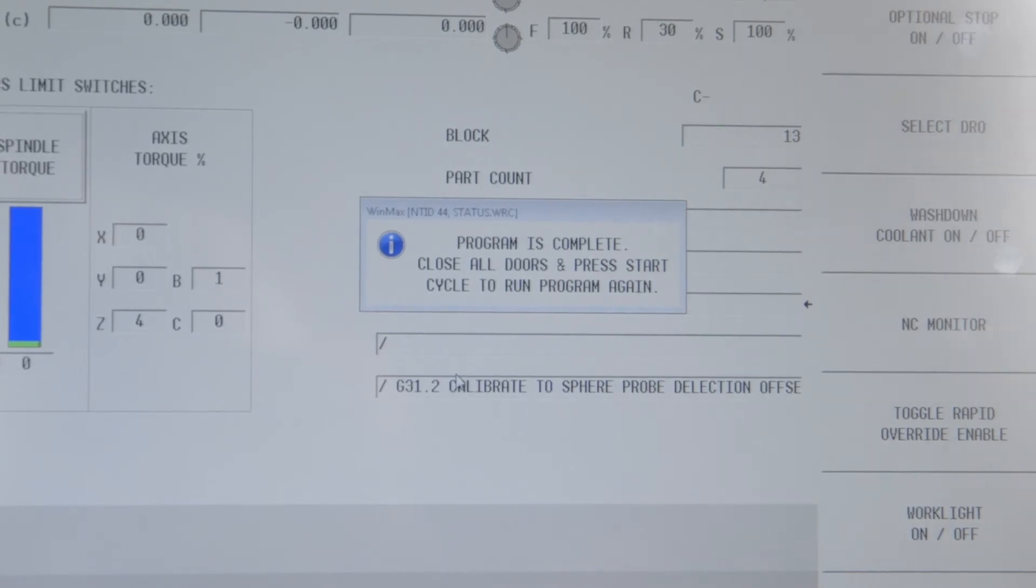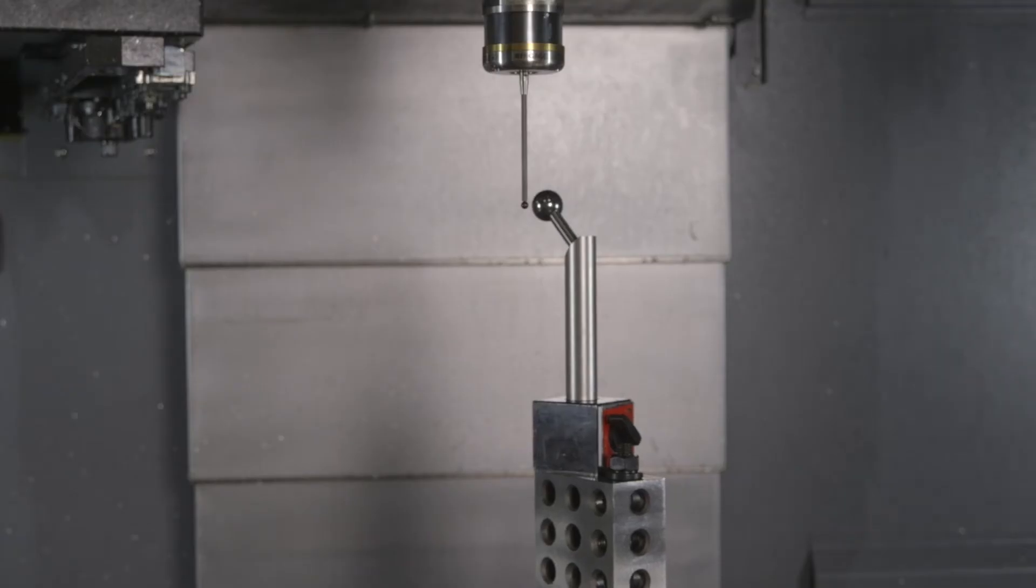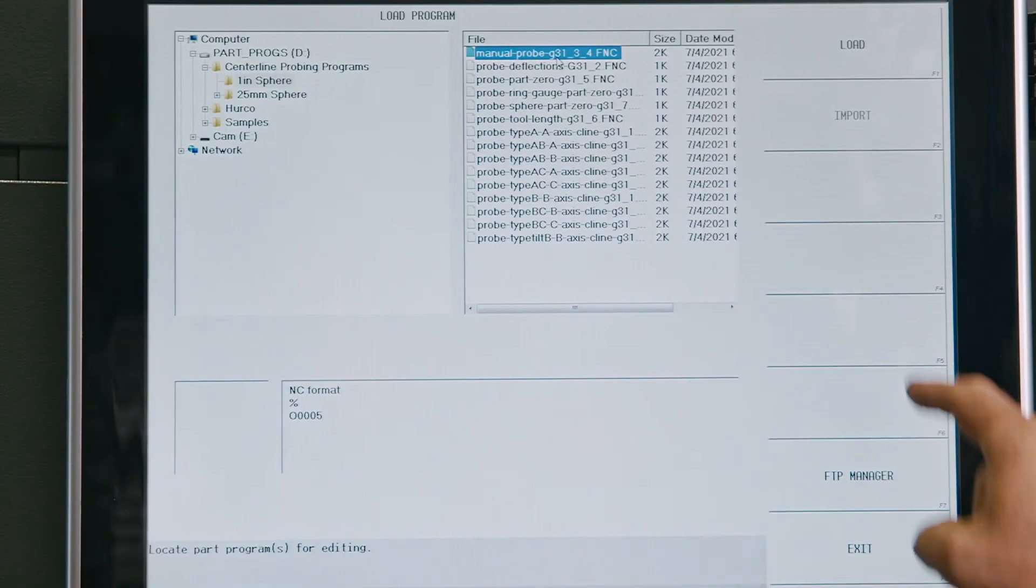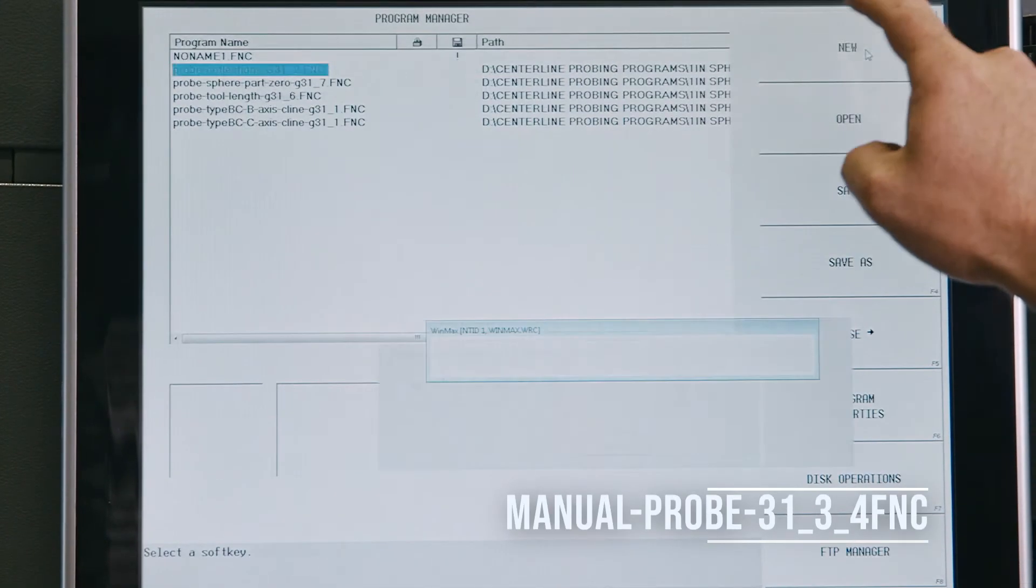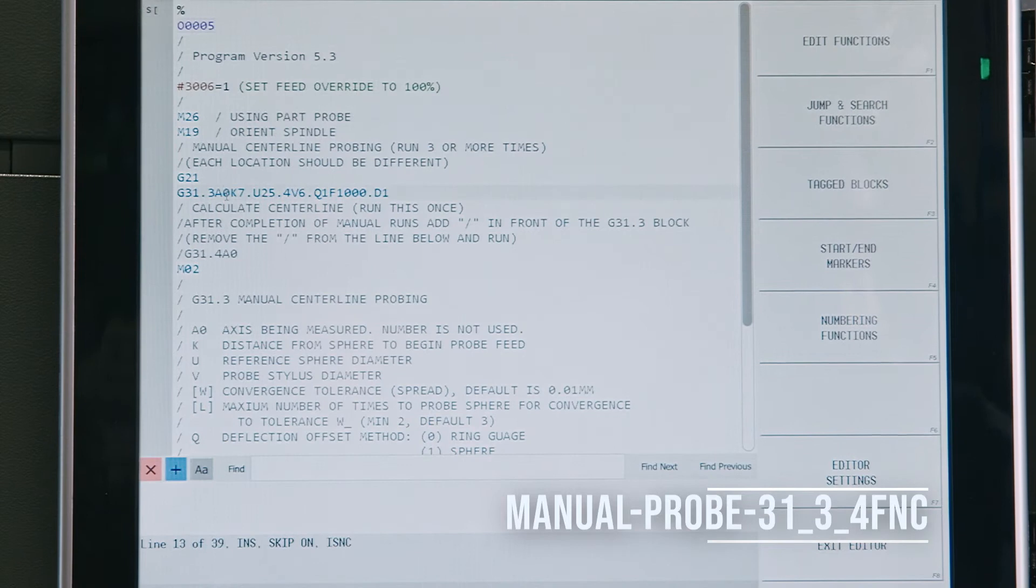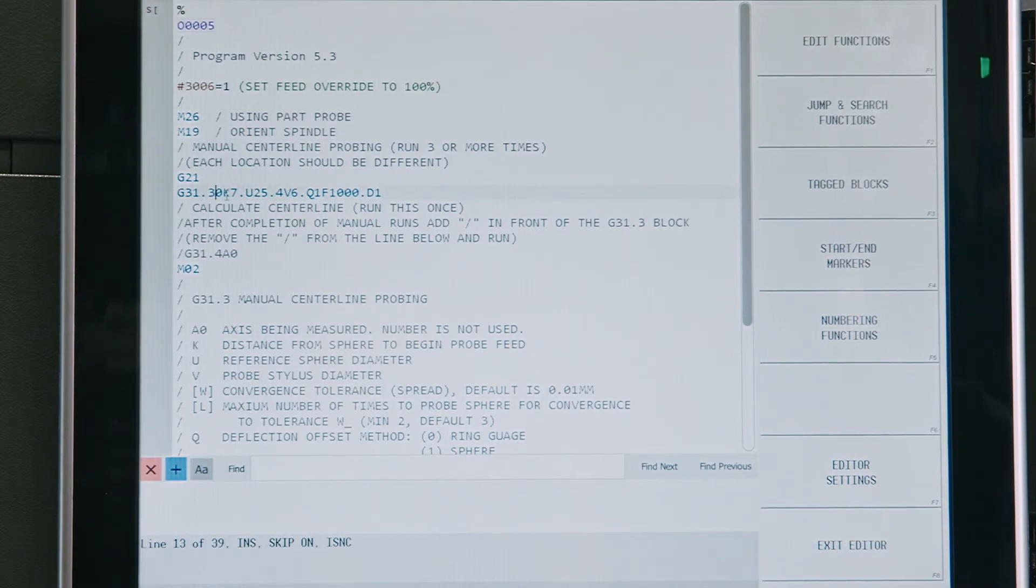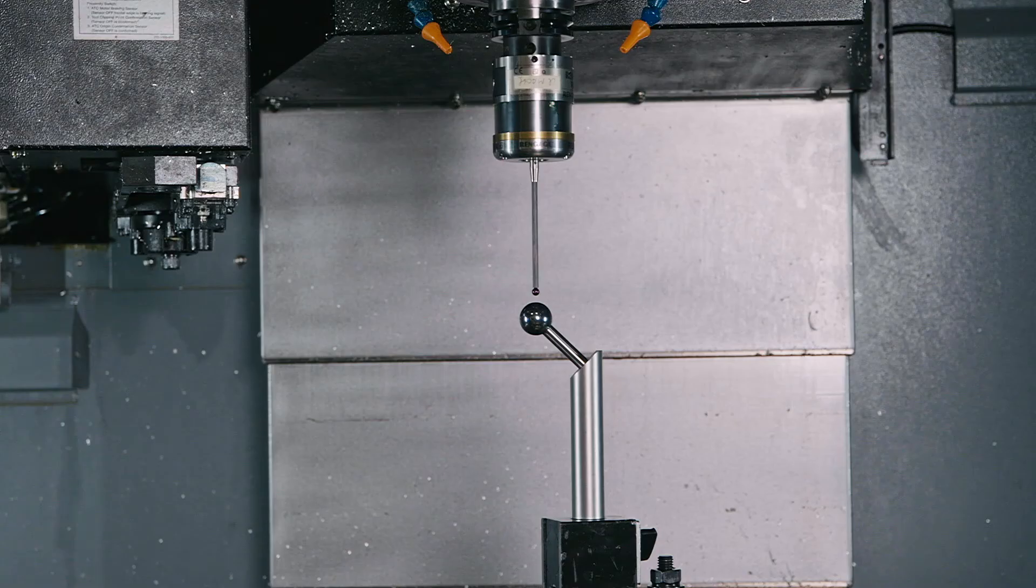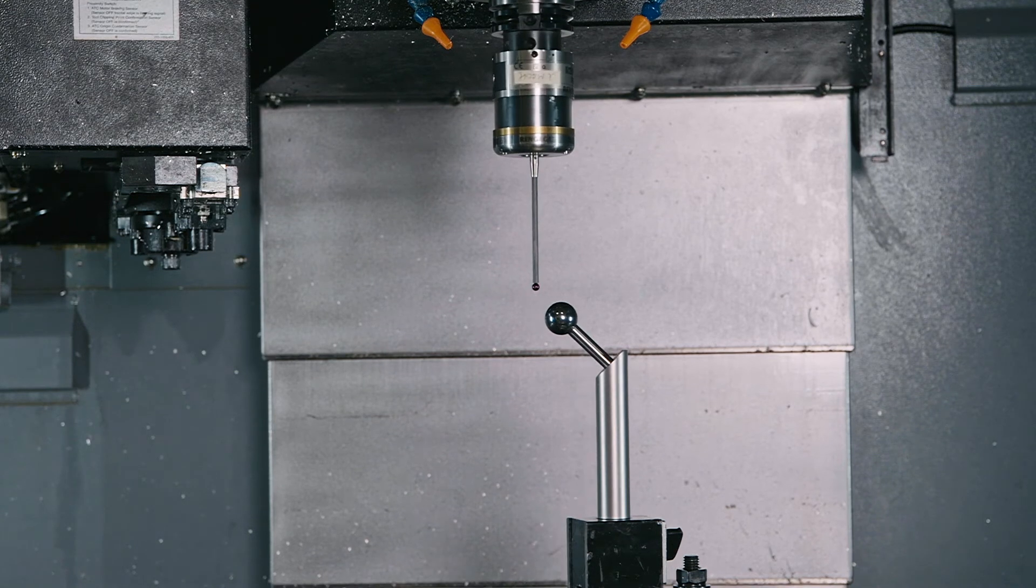If center lines are unknown or over a millimeter out, we follow the manual procedure by first loading program manual probe G31-3-4 FNC. Change the axis in both G31 lines to the axis you want to probe. Manually position the probe about a quarter inch from the sphere and run the program.